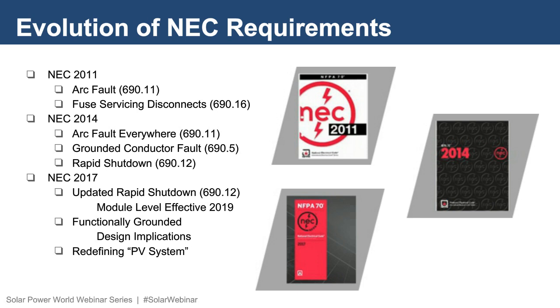In the 2017 NEC, a major revision occurred. Of the many changes, notable ones are the redefinition of the PV system boundary, a new definition of functionally grounded, a major overhauling of rapid shutdown, and arc fault now has an exception for systems not on or in buildings.